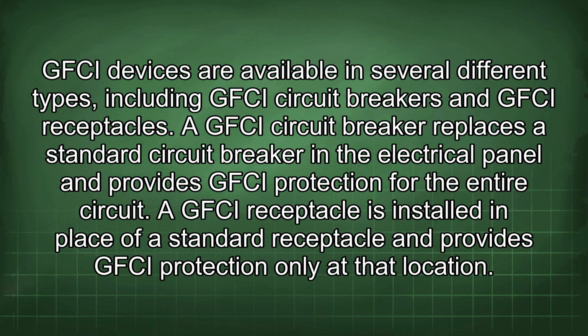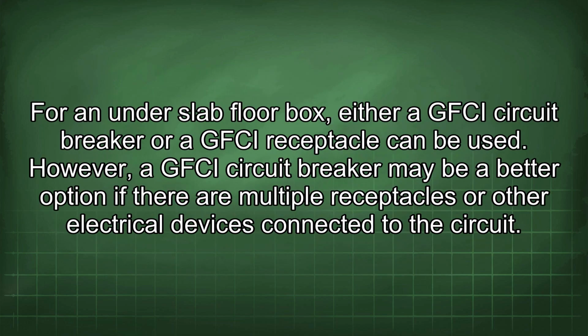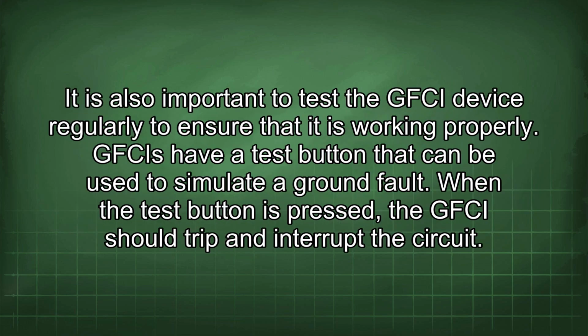GFCI devices are available in several different types, including GFCI circuit breakers and GFCI receptacles. A GFCI circuit breaker replaces a standard circuit breaker in the electrical panel and provides GFCI protection for the entire circuit. A GFCI receptacle is installed in place of a standard receptacle and provides GFCI protection only at that location. For an under-slab floor box, either a GFCI circuit breaker or a GFCI receptacle can be used. However, a GFCI circuit breaker may be a better option if there are multiple receptacles or other electrical devices connected to the circuit.